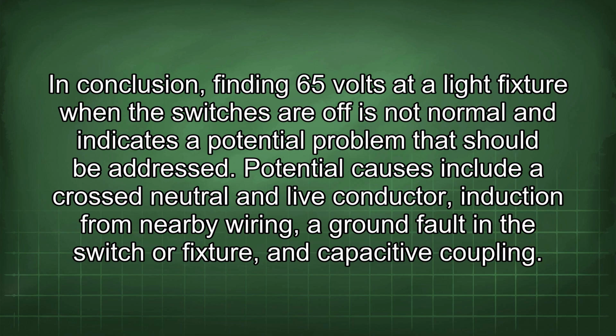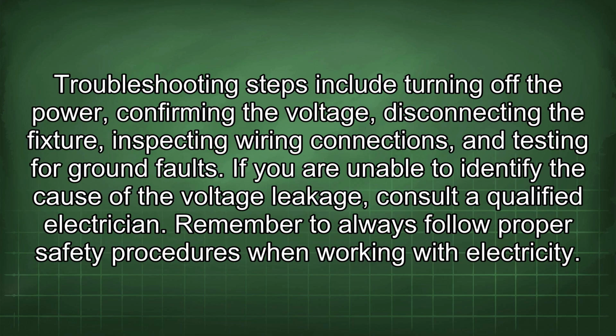In conclusion, finding 65 volts at the light fixture when the switches are off is not normal and indicates a potential problem that should be addressed. Potential causes include a crossed neutral and live conductor, induction from nearby wiring, a ground fault in the switch or fixture, and capacitive coupling. Troubleshooting steps include turning off the power, confirming the voltage, disconnecting the fixture, inspecting wiring connections, and testing for ground faults. If you are unable to identify the cause of the voltage leakage, consult a qualified electrician. Remember to always follow proper safety procedures when working with electricity.